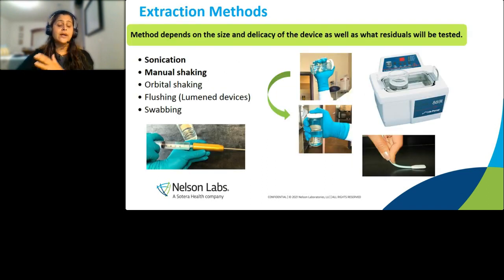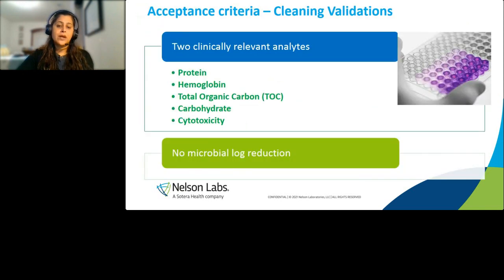Once all that is done and we've cleaned the devices, now we're extracting them. There are different ways of extracting devices. As you can see, we flush if there are lumens, there is manual shaking, and if there are computer screens or non-critical devices like we saw at the beginning of the presentation, we would use swabbing. Once they're extracted, we test for analytical markers: protein, hemoglobin, total organic carbon. All of this is what we're looking at when we're doing these validations.